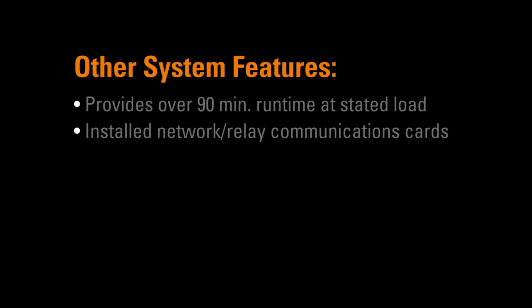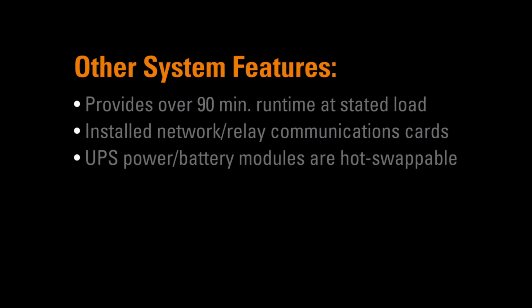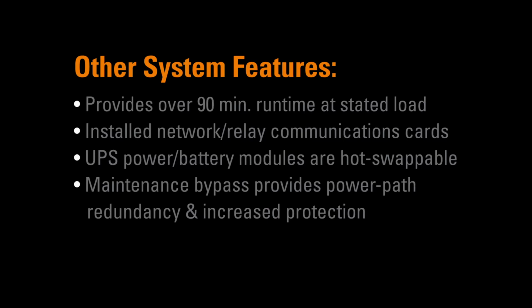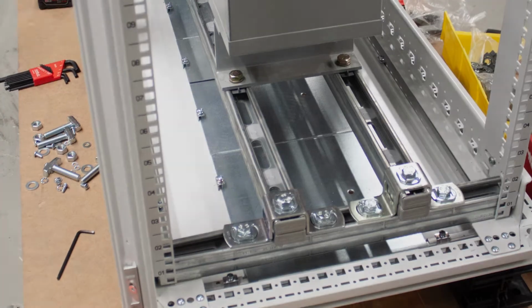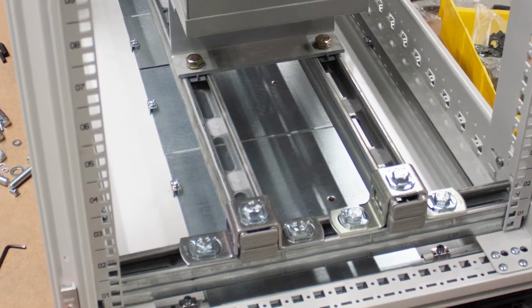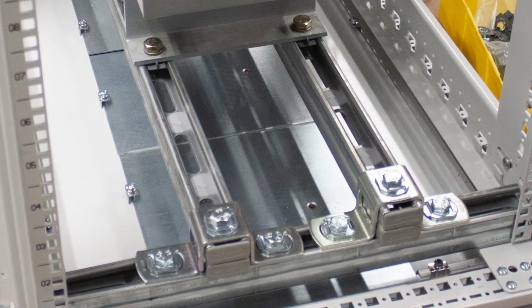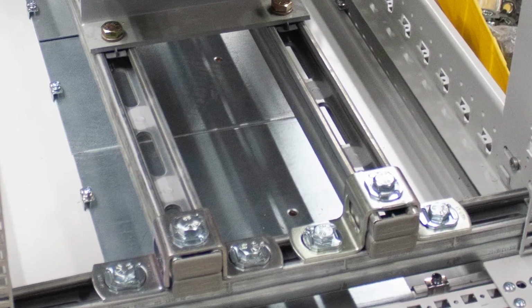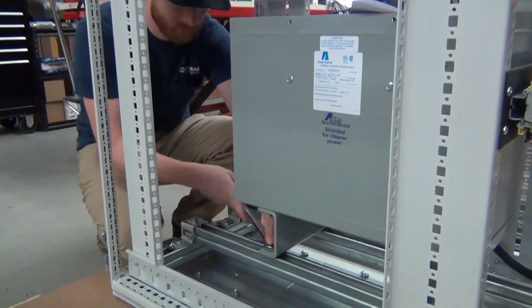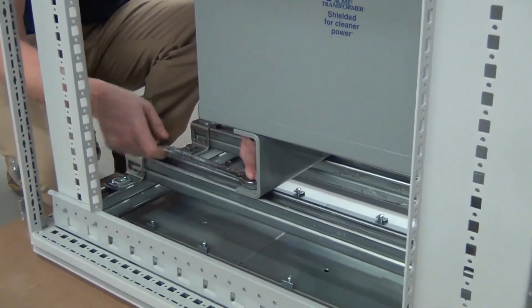A network communications card and relay communications card were also installed. The UPS power module and battery modules are user replaceable and hot swappable. The supplied maintenance bypass provides power path redundancy and a greater degree of protection in the event of an unscheduled shutdown. Unistrut was used to fabricate the custom mounting structure needed to support the 600-volt to 208-volt step-down transformer. The channel system was bolted through the enclosure frame, providing a strong, secure attachment for the transformer.